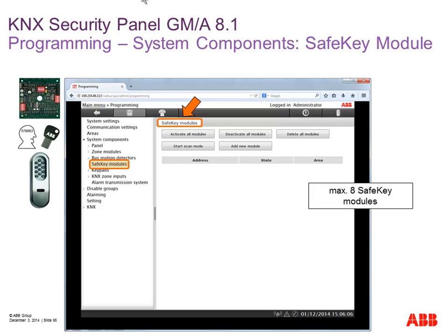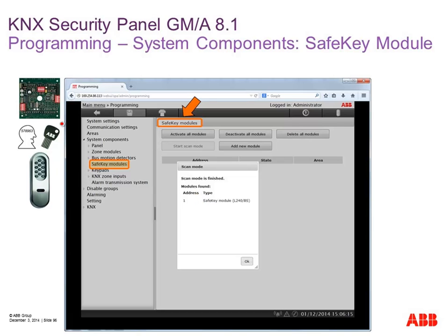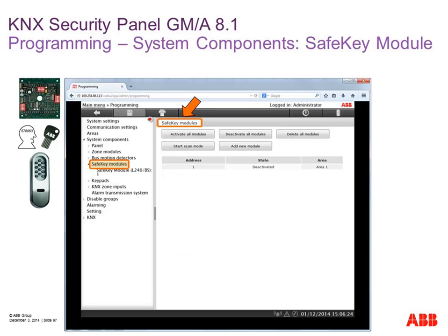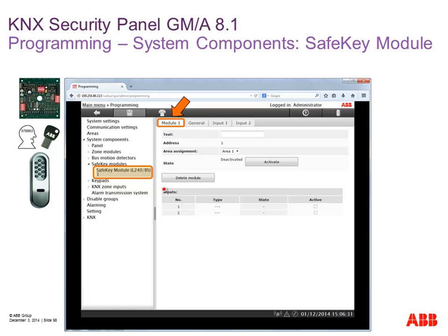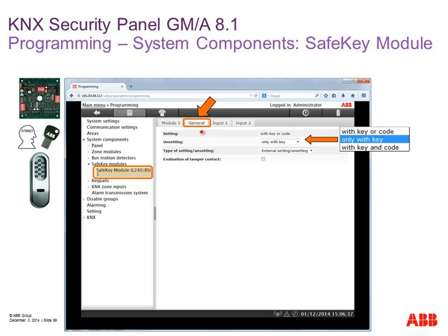The next module is the safe key solution. We can connect the safe key module for direct setting: it's installed inside nearby the door. We connect the magnetic reed contact, door lock contact, and our arming device installed outside the building. Via key or via code we can set and unset the system. The easiest way is to start 'scan mode' — press the button and the panel scans the bus, finding the module with address number one depending on the DIP switch.